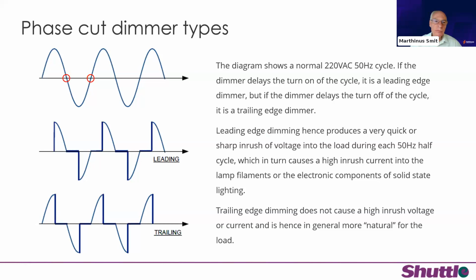If we look at the waveform on the top left-hand side here, this is a beautiful sine wave. That's what the voltage looks like when it comes out of your main supply. Now, importantly, I've encircled in red the crossings where the voltage crosses from positive to negative, and when the voltage crosses from negative to positive again, because that is where your dimmer actually synchronizes with your mains. Your dimmer has to be very, very synchronized with the AC mains, and we'll get to that as a problem a bit later. And in leading edge dimming, as you can see in the second waveform here, when the AC voltage crosses through zero, initially the dimmer leaves the lamp off, and then somewhere in the cycle the dimmer would actually turn the lamp on.